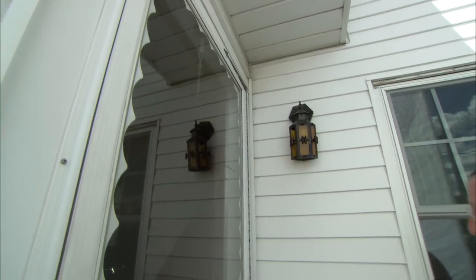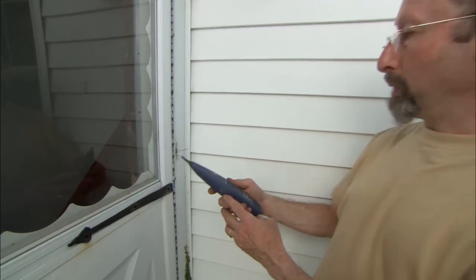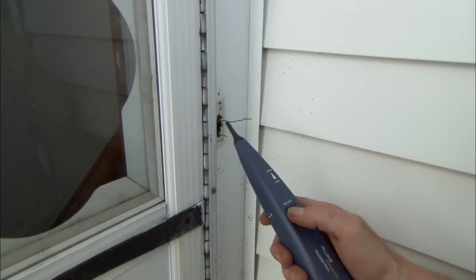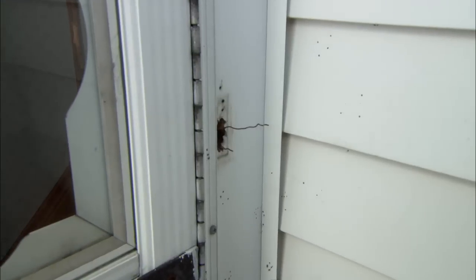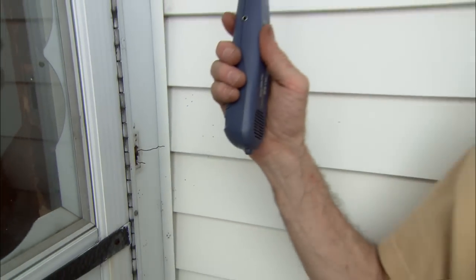So we are transmitting a radio signal from the basement, hopefully across these wires right here, and we'll prove that with a receiver. This is a tone probe and it's designed to pick up the radio signal. We have a good signal on the first wire. Now let's test the second wire — we get nothing. Well, we need both those wires. This wire is broken — somebody broke it, somebody disconnected it over the years.